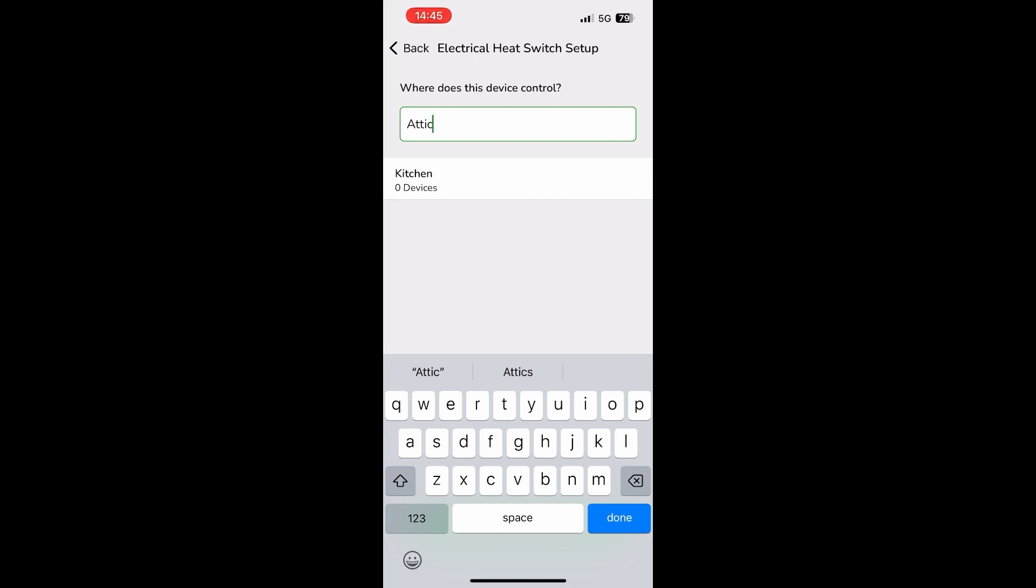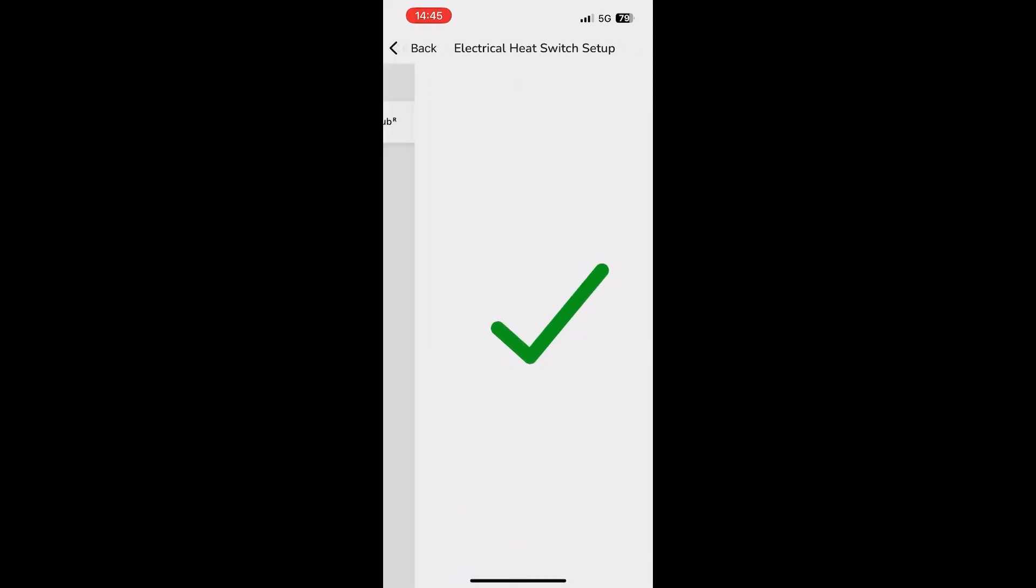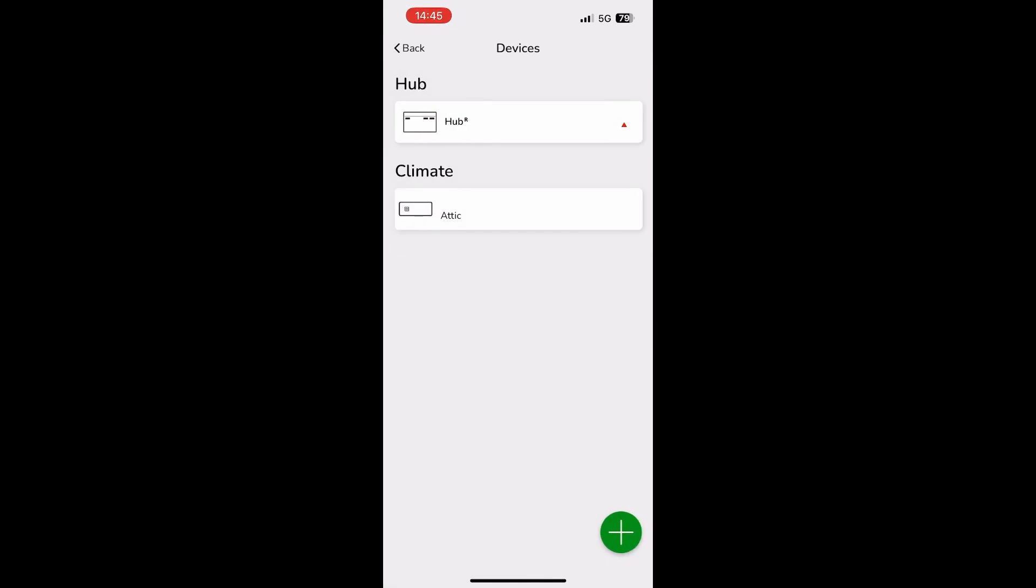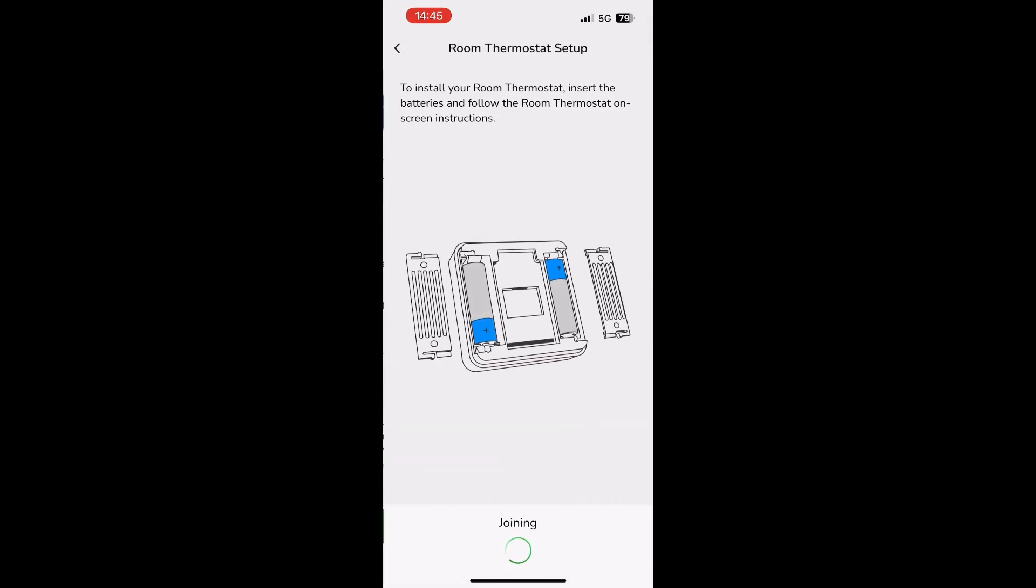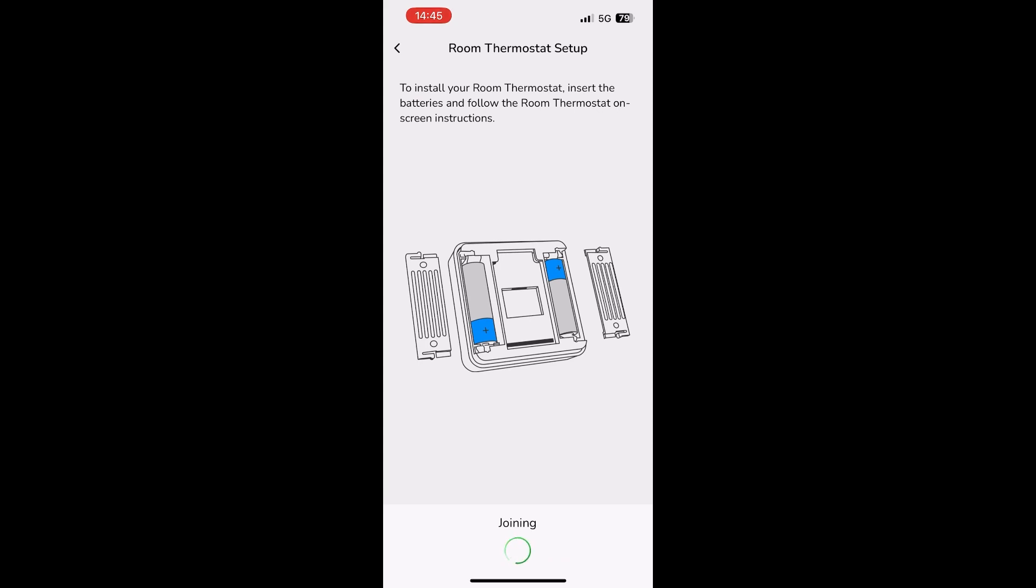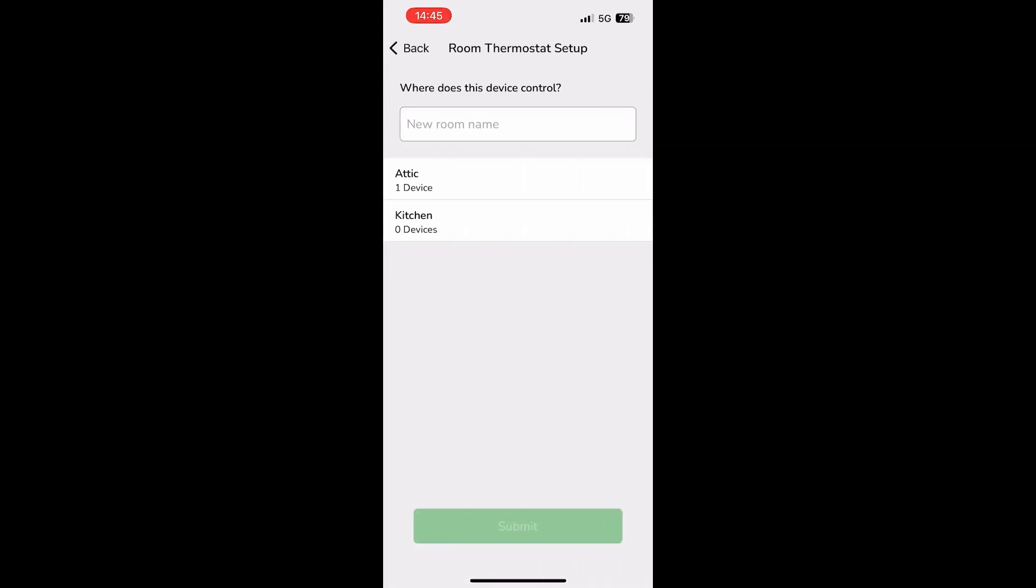The app confirms that the zone has been successfully created, but before you can start controlling the zone you need to assign a Wiser room thermostat. So back to the landing page and this time you pick the room thermostat option. Insert the batteries into the Wiser room thermostat and wait for the device to join the network. Once the device joins, it needs to be assigned to the same zone as the electrical heat switch. In this case, the attic.